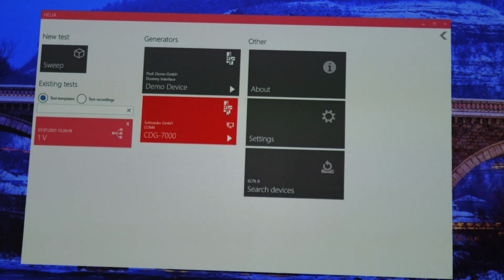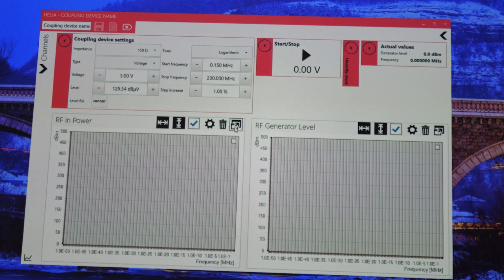And once I'm back at the main menu, before I begin running a test, I'm going to go into test level and I'm going to create a calibration file for my CDN. Once this opens up, I can go into the name and I'm going to name my coupling device a CDN M5, since it's a 5-line CDN, 63 amps because it's 63 amps per phase, and 1000 volts since this particular CDN can do something like close to 700 volts AC and then 1000 volts DC.